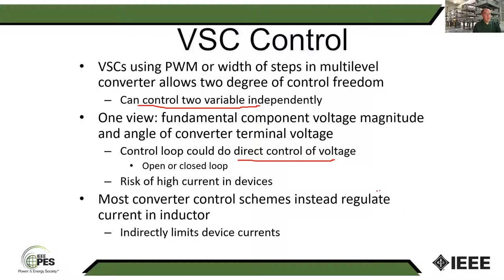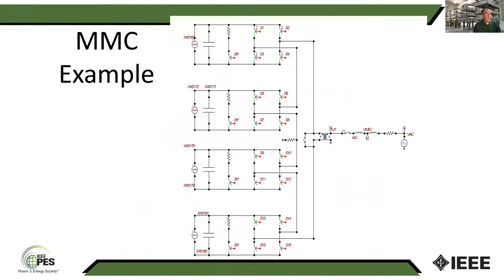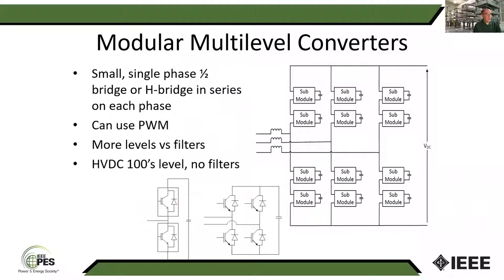But most schemes that you would see used for rooftop PV systems, for large photovoltaic systems, for wind turbines, are all using something where you have a scheme to regulate the current in the inductor. The reason they do that is that these power electronic devices have limits to how much current they can carry, and they cannot carry overcurrent. So you can put a fault on a synchronous generator and it can supply like five or six per unit current for the length of time it takes you to clear the fault.